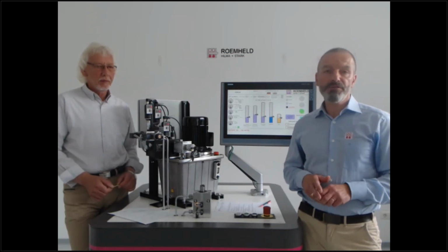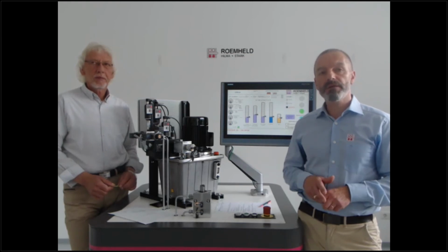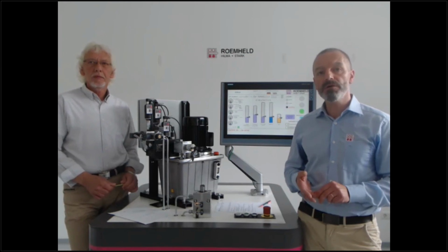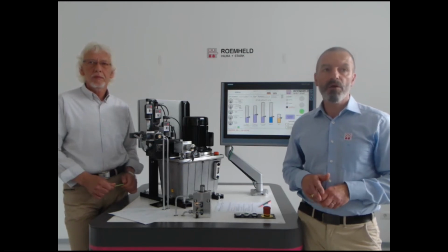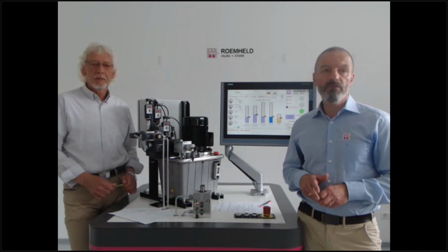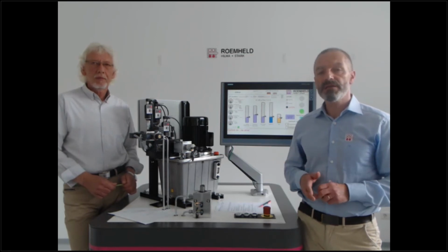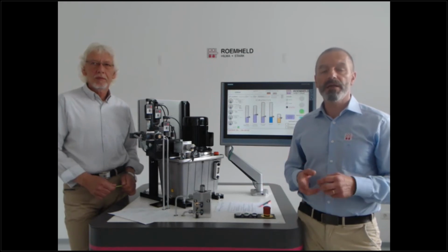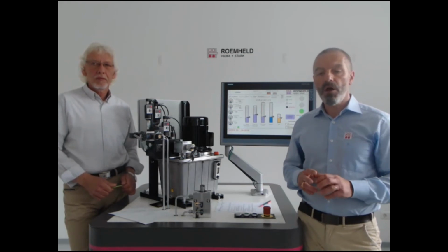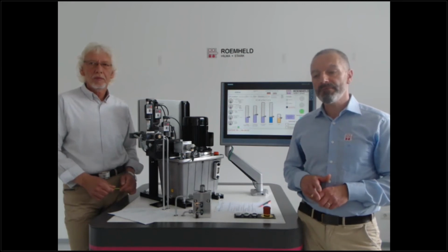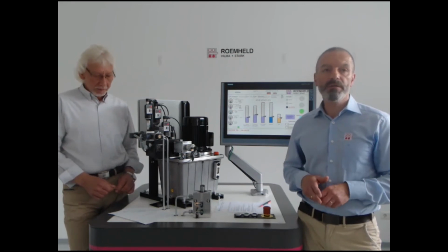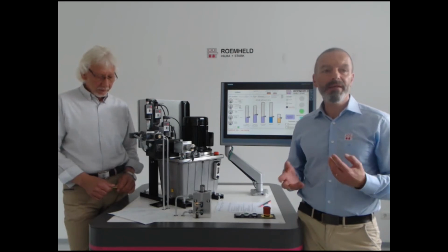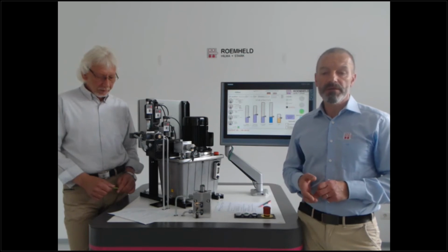So the influences are quite different, as well as the connected components. It's a huge difference between single and double acting components. As I said earlier, single acting components normally need venting, and by venting, by experience, a lot of particles can enter the system. But all that is something we can also pass on as recommended values, depending on the different application you may have.